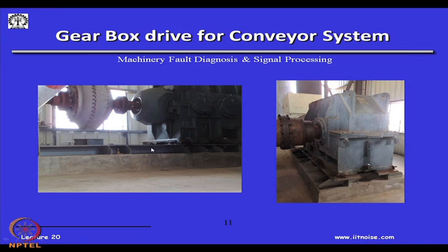At this location, this was about 100 meters from the ground, on a platform made out of concrete. The conveyors were coming out from large ships and they are high over the ground, and obviously, if this floor is not level, this system could have a misalignment. So, a lot goes into ensuring that the shafts between the motor and the gearbox are level, in the same horizontal plane. Even a variation of a few millimeters or microns is going to affect the dynamic forces. So, perfect alignment has to be done.